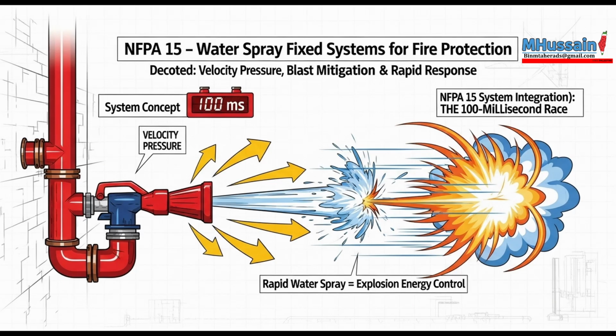Why the higher pressure for small orifices? You need that extra pressure head to really ensure the spray pattern forms correctly and maintains its shape against wind or other interferences. Get the water where it needs to go. Makes sense. Now, let's tackle the big one. The cornerstone of complex NFPA 15 hydraulics, something often simplified or even ignored in less demanding systems. The velocity pressure correction, Pv, that's 8.1.4. Why is Pv so critical here, unlike in, say, most NFPA 13 sprinkler calcs? The key difference is velocity. In standard sprinkler systems, NFPA 13, water velocity might hit maybe 15 feet per second, rarely much higher.